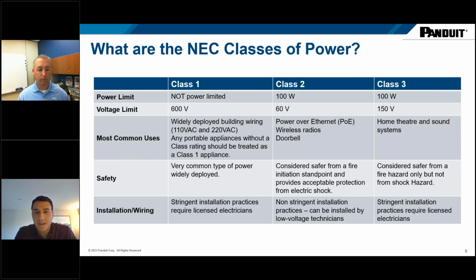and one of the most common applications of it is power over Ethernet. The power part in the PoE is considered Class 2. And by limiting, these are considered limited power sources. By limiting the power and the voltage, it's considered safe from a fire initiation and a shock hazard perspective. And therefore, now you can have a low voltage contractor install Class 2 circuits.